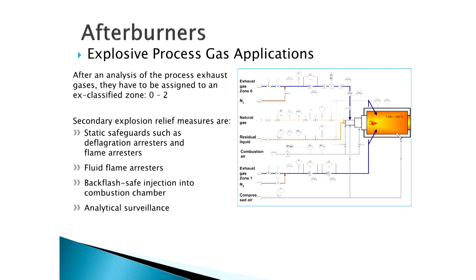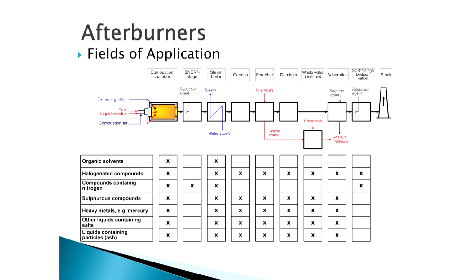You might be thinking about an enclosed flare. It's a little different from an enclosed flare in that we can handle both oxygenated and oxygen depleted gas streams with this device. This is just an example of the different fields of application of this particular device. On the front end of this schematic, you see the afterburner, and after that there could be many other different devices, depending on the constituents we see and the things that we're generating as a result of the combustion process. So we could have SNCR after it.